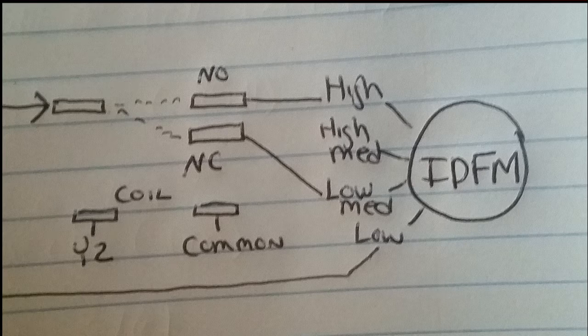If the Y2 gets a call from the thermostat, it's going to energize the coil. It's going to cause the relay to switch from normally closed to normally open. So it's going to pass from the cooling tap to normally open and switch the blower speed to high. So once the compressor goes into high cool, our blower will go into high speed. Keeping in mind that this is an example, you're going to want to verify and get the airflow as close as possible. One of the flaws with the plan is that the airflow won't be designed from the manufacturer, so you're going to have to match it up to what you think it should be based on the manufacturer settings for the 2-speed unit.